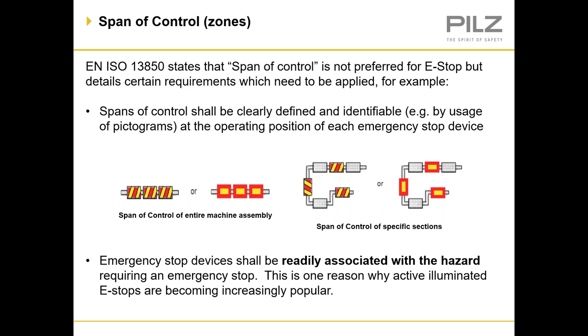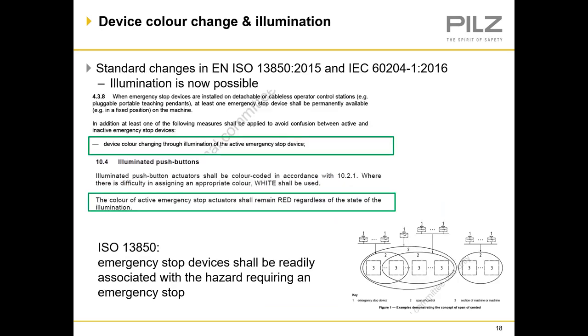This is one reason why actively illuminated emergency stops are becoming increasingly popular. Standard changes in EN ISO 13850 and IEC 60204 mean that illumination is now possible. Section 4.3.8 of standard EN 13850 covers when emergency stop devices are installed on detachable or cableless operator control systems — for example, pluggable, portable or teaching pendants. At least one emergency stop device shall be permanently available in a fixed position on the machine.